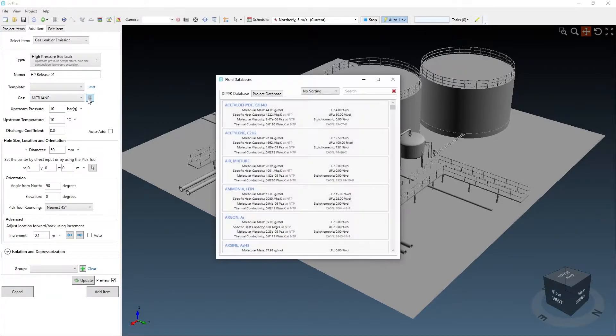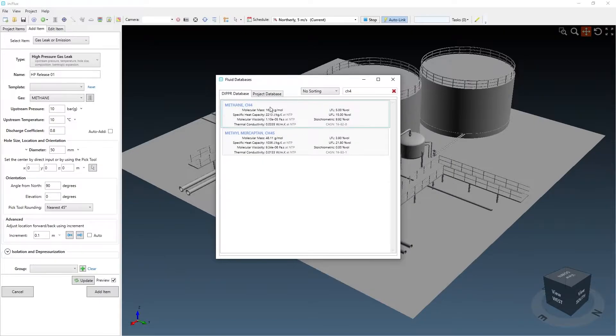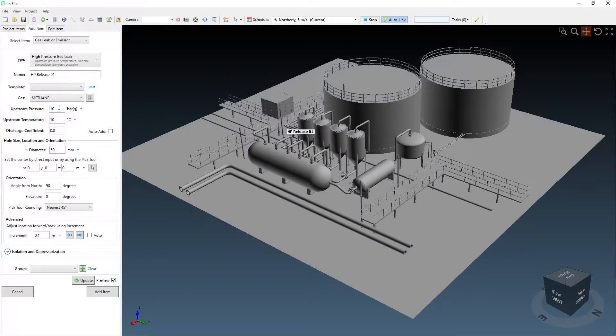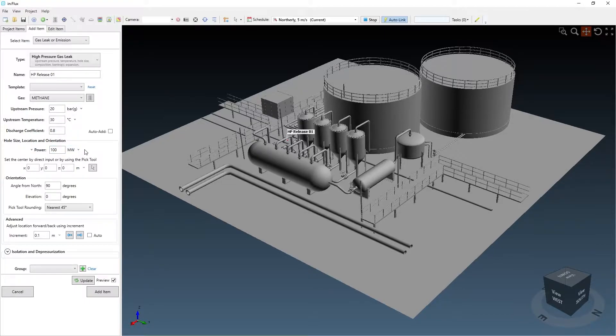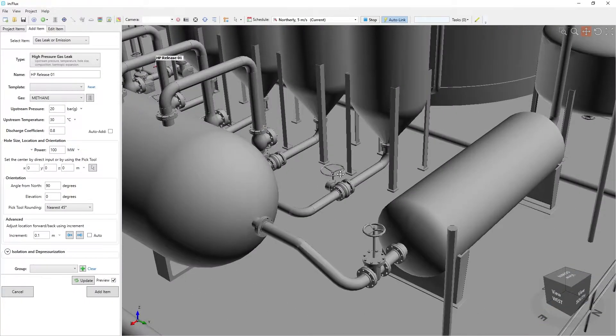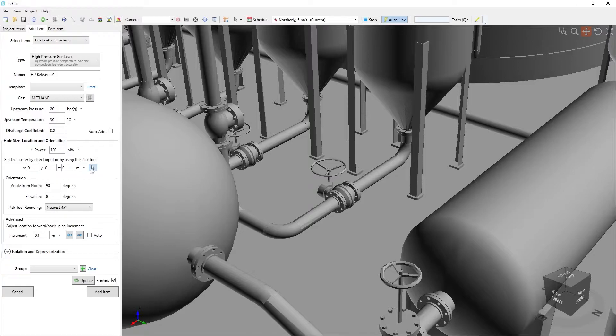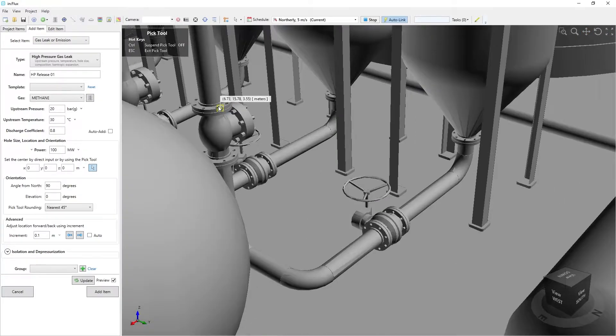Inflows can be defined as a single component or multi-component mixture using the included fluids database. Various options exist for defining the size of the leak, such as diameter, flow rate, or power. Here I will set up a 100 megawatt jet fire case using a high pressure release and position it to be directed towards a vessel.